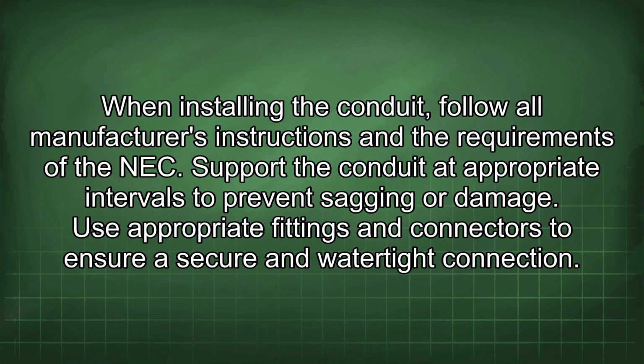When installing the conduit, follow all manufacturer's instructions and the requirements of the NEC. Support the conduit at appropriate intervals to prevent sagging or damage. Use appropriate fittings and connectors to ensure a secure and watertight connection.